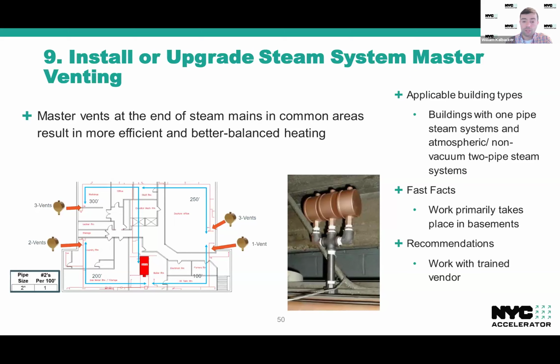So if you have a comprehensive master venting setup in your building, then it's very easy for that air to escape in between cycles, and your boiler does not have to work hard to fill the system back up with steam at the start of a cycle, which is why master venting is recommended and a requirement here. So this is going to be required for all one-pipe steam systems, as well as two-pipe steam systems that work at atmospheric pressure. So master venting is not going to be required for two-pipe systems that run on a vacuum.